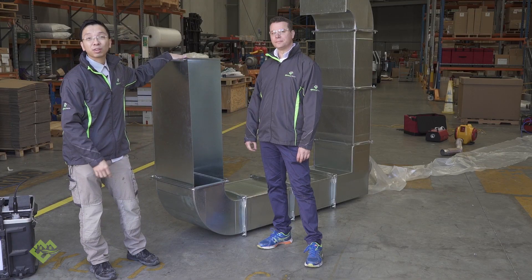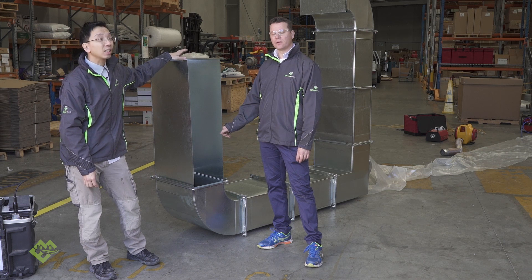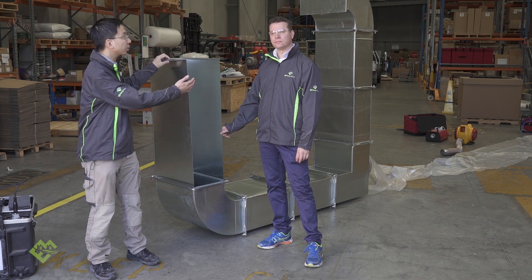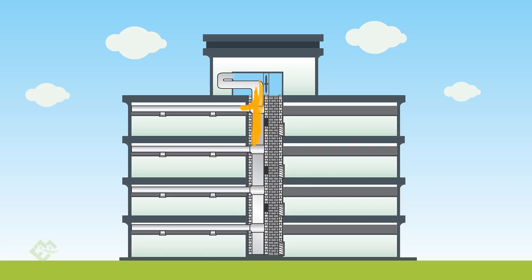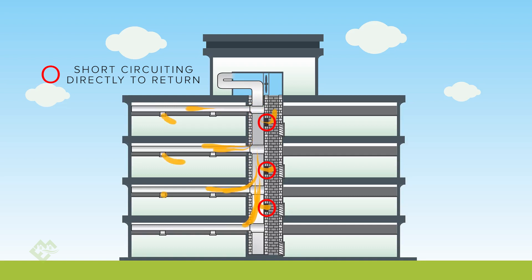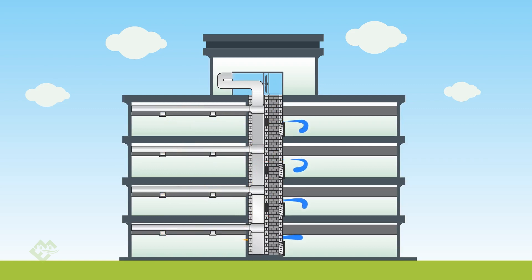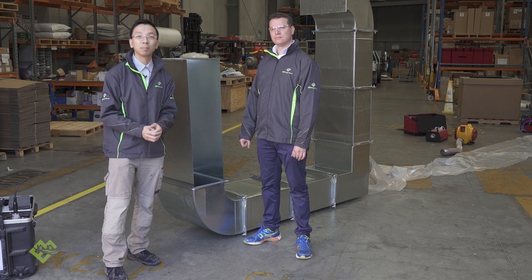Beyond wasting 35 percent of conditioned air, leakage also messes up your control systems. The conditioned air may leak directly into the return air path, causing conflicting signals — the thermostat in the room says you need more cooling, but the return air temperature sensor at the air handling unit says it's already cold enough. The control system simply doesn't know what to do, which can have a very significant energy implication.